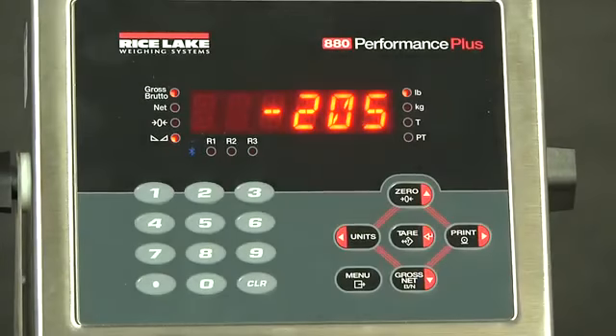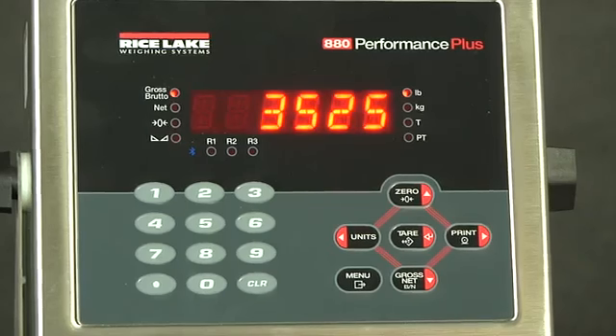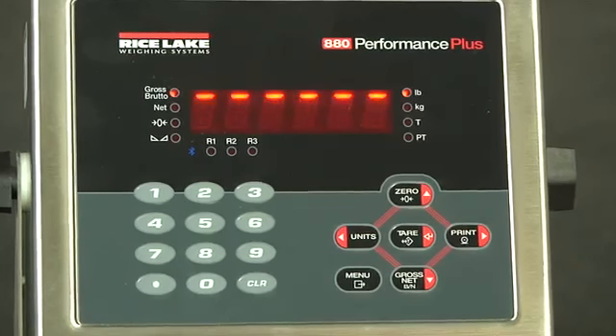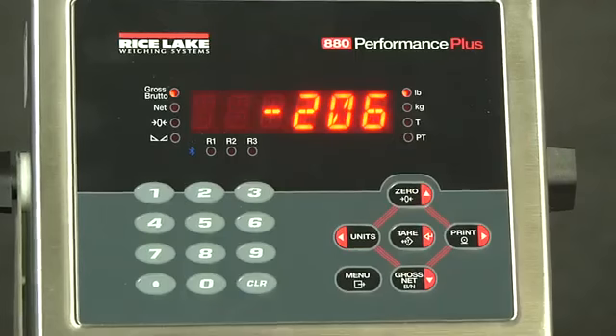Today we have the 880 indicator and we will be walking through configuration and calibration. As you can see now, at 0 millivolts we are currently sitting at negative 205 pounds. If we crank it up, we go off the spectrum at 2.0 millivolts. So what we want to do is actually configure this for a 5,000 pound scale counting by 1 pound, and we will go up to 3 millivolts.